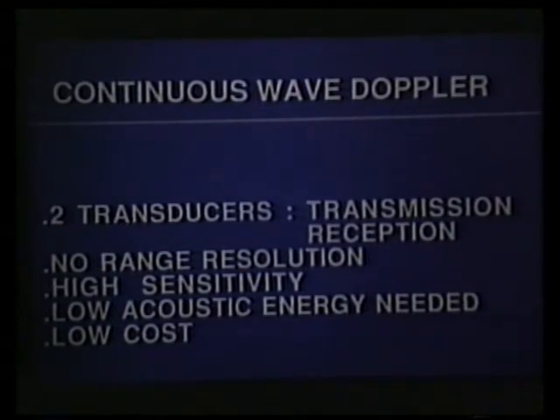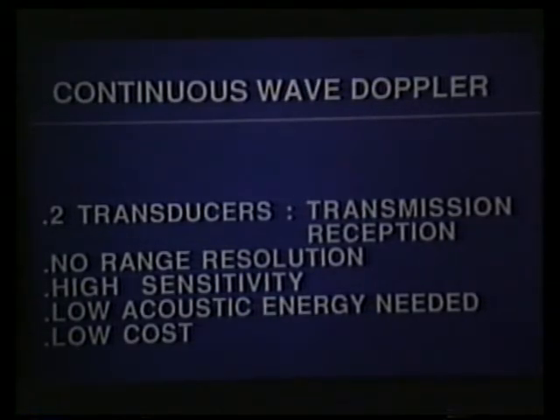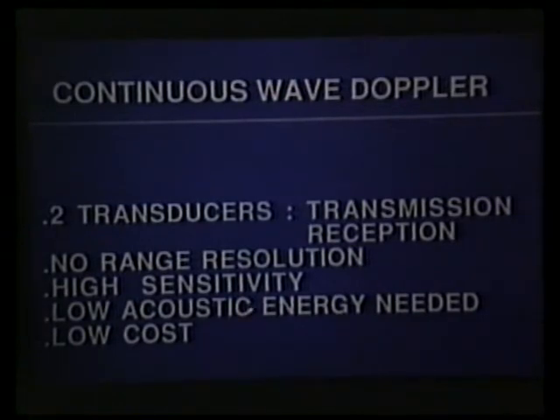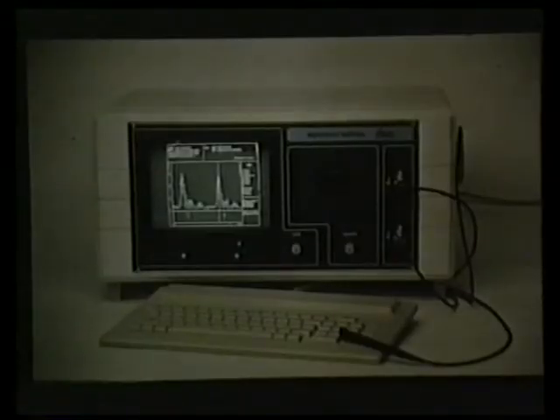In a continuous wave Doppler device, signals are received from every moving reflector in the path of the beam, so there is no range resolution. The advantages of this continuous wave Doppler system are its high sensitivity, the need for low acoustic energy, and its relatively low cost.